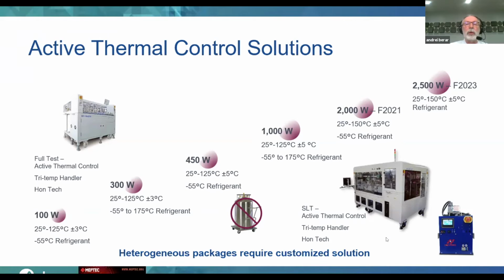This has moved away from traditional air cooling, which is running out of steam so to speak, to more liquid cooling. All these applications use liquid cooling at various levels, using chilled liquid, and for most regions down to minus 55, we need to use refrigeration technique.